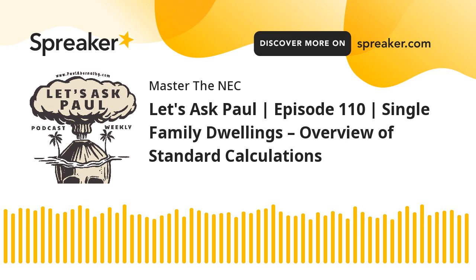And then, of course, you understand the rules of 220.14(J). And so that's why we can apply 220.42. Make sense? Okay. So now we came up with that total value. And we took all the general lighting and receptacle loads at 3 VA per square foot. We took the minimum of 2 small appliances, and we took the minimum of at least 1 laundry. And we take those values and we add them up, and now we come over to this table.